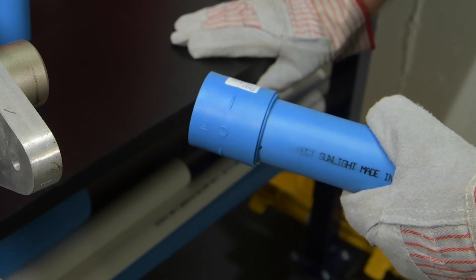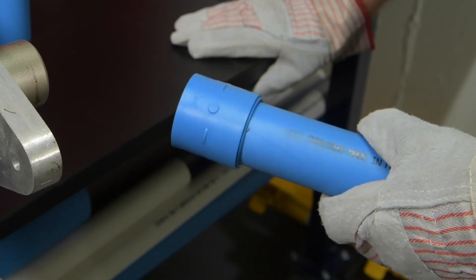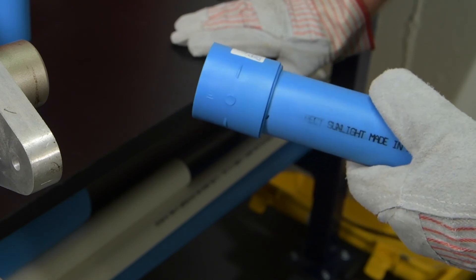The melted surfaces will begin to fuse within 5 to 7 seconds of being removed from the tool. Any attempts to straighten or otherwise alter the joint after this time will break the weld, resulting in a leak. Do not stress newly fused joints until fully cooled to ambient. Do not douse the cooling joints with cold water.